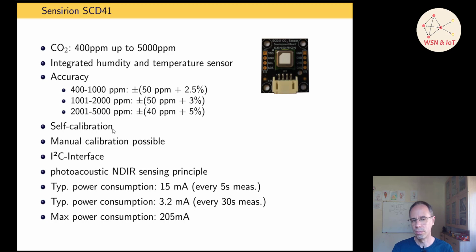You're seeing here that the accuracy depends also a little bit on the ppm amount from carbon dioxide. It has the same self-calibration and manual calibration options available. It has the infrared I2C interface and uses a photoacoustic measurement sensing principle, which is patented. This is why they can make it much smaller.